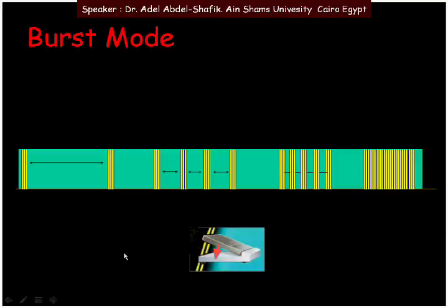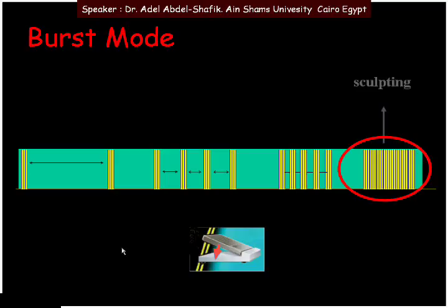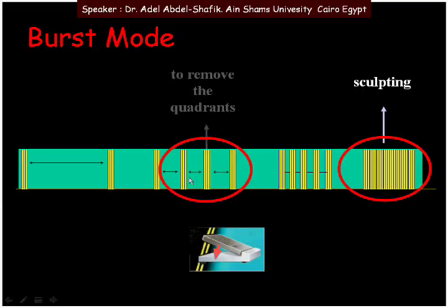Applying this to burst mode: when the pedal is pressed deeply into position three, we have continuous phaco, which can be used for sculpting. With the pedal midway in position three, we have intervals of on and off, which is suitable for removal of quadrants.